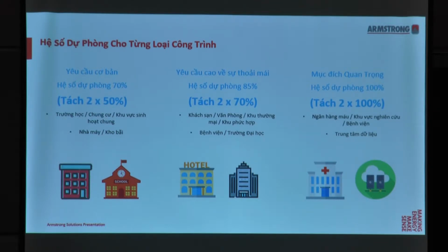So we propose maybe you can consider 2 by 50% capacity split, and this thereby gives you 70% flow redundancy. And next, if you're designing perhaps high comfort sensitivity, such as hotels, offices, universities, or campus, you can consider 2 by 70% capacity split, giving you 85% flow redundancy.